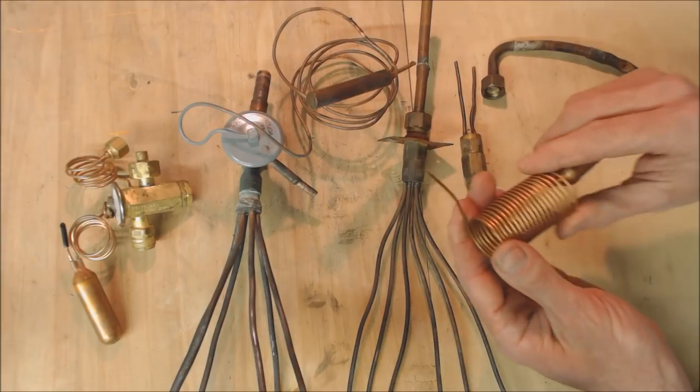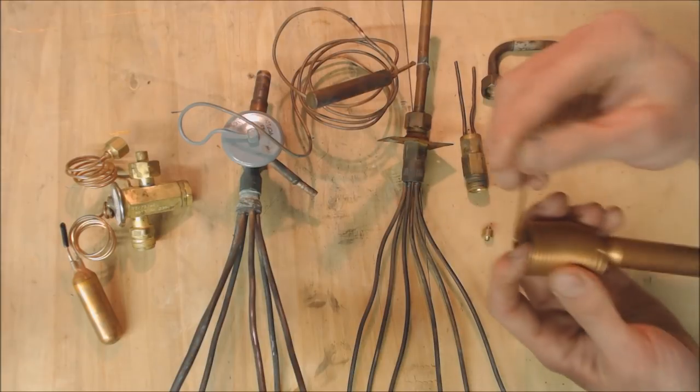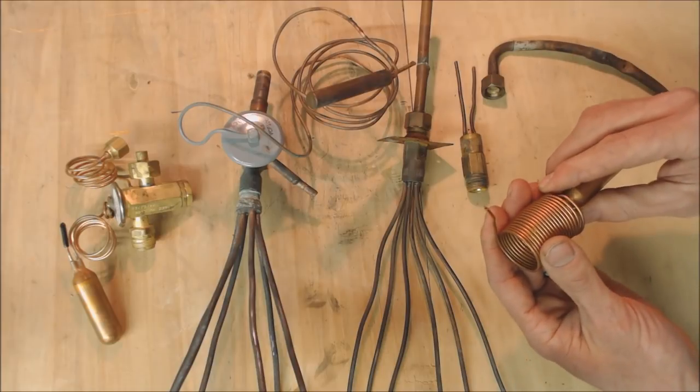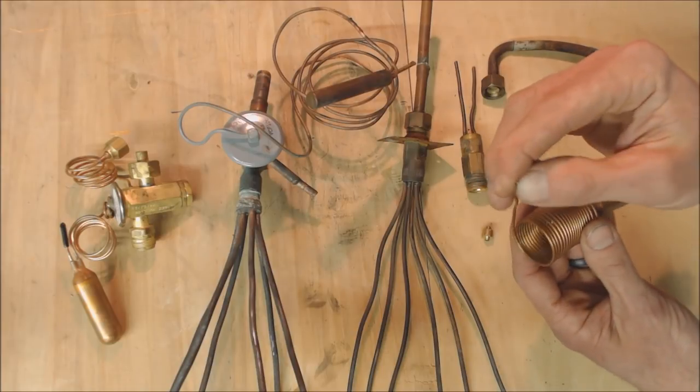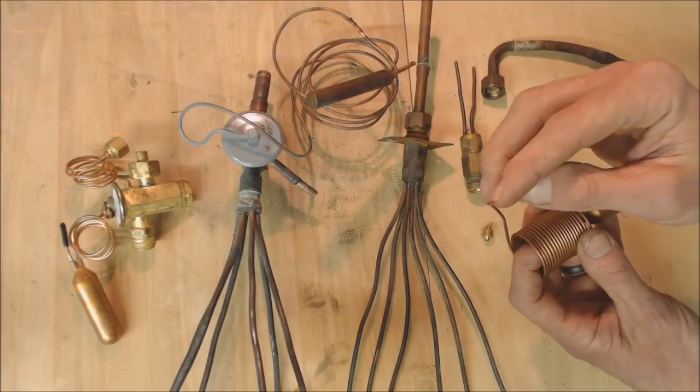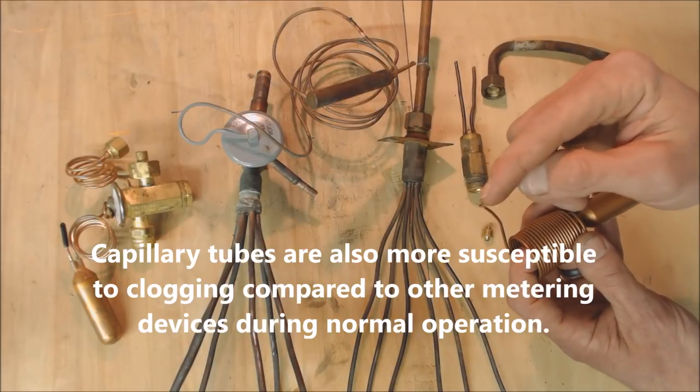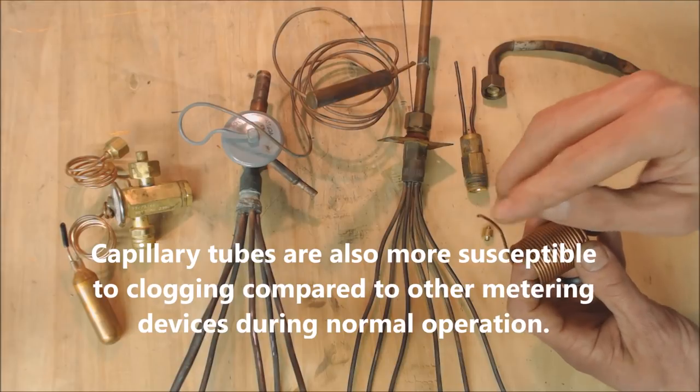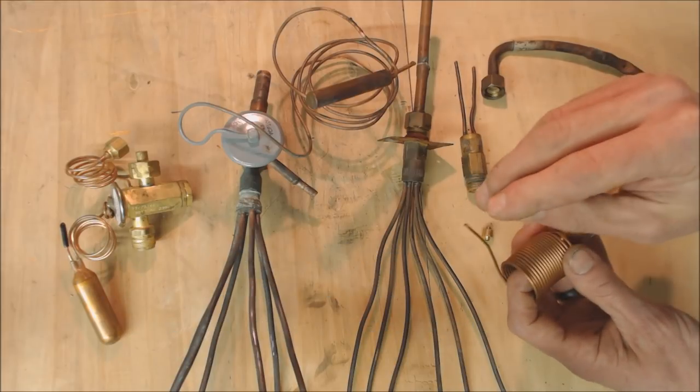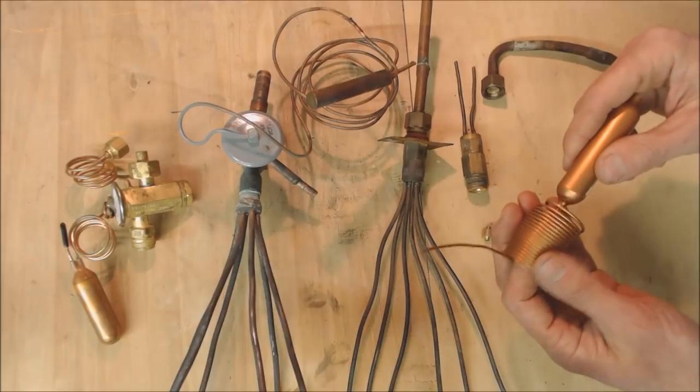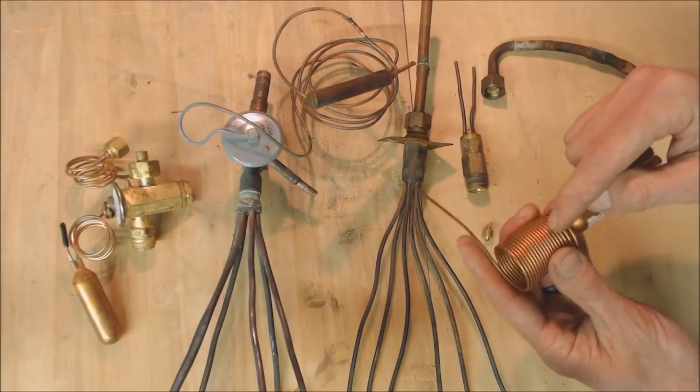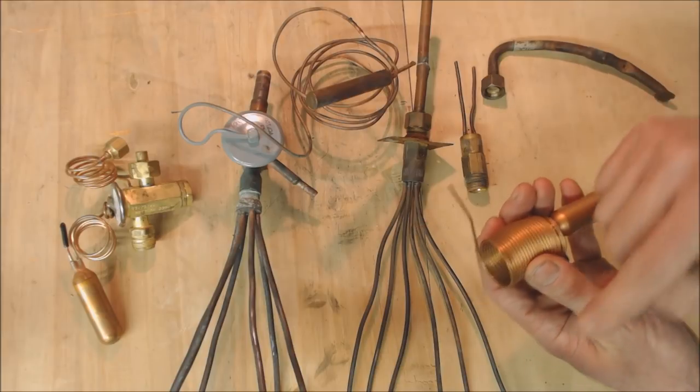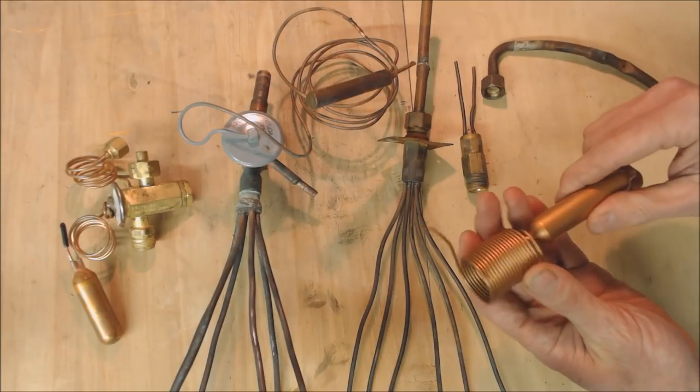With these, they're not easily changed if you want to change the size. You have to unbraze it and replace it. During the brazing process, it's easier to accidentally clog the cap tube with braze if you spend too long brazing or put too much on. This also does not have a bypass built in for a heat pump, so you'd have to have an external bypass around the capillary tubing.